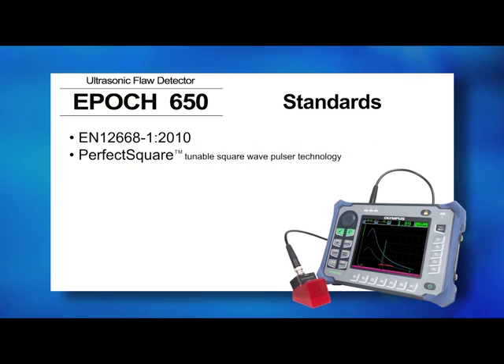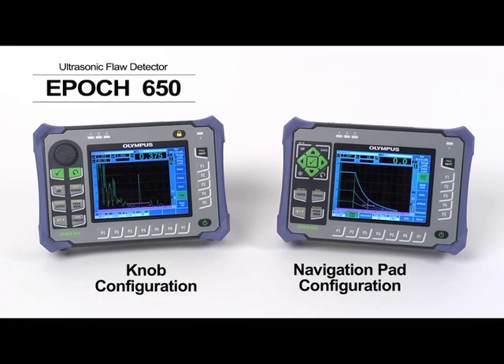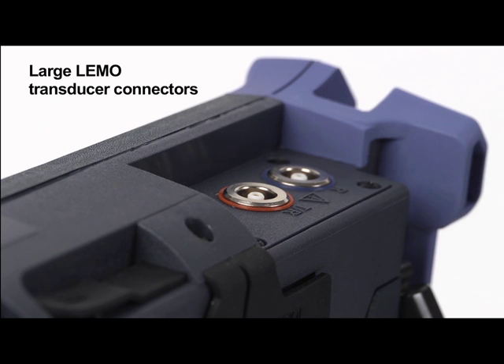This newest addition to the EPOCH family is designed to meet the standards of EN12668-1:2010. It comes standard with our perfect square tunable square wave pulser technology, a full screen A-scan mode, and multiple inspection technique features such as DAC-TCG, DGS, and our AWS-D1.1/D1.5 indication rating calculator. The EPOCH 650 is available in either a knob or navigation pad configuration to meet the preferences of any user, and can be configured with BNC or large LEMO transducer connectors.